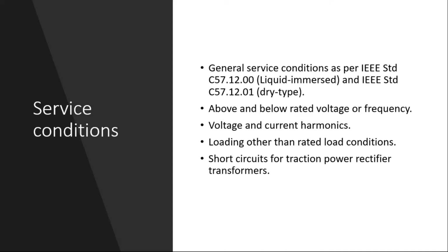And next one is the harmonics. The voltage and current harmonics are specified in standard 519. So it gives what the harmonics limits are for the different voltage classes, and that has to be taken care of. If the harmonics are more than the limit, then we have to do additional calculations for cooling requirement. And for traction application transformers especially, we have special duty requirements, which we have covered in the upcoming slides.